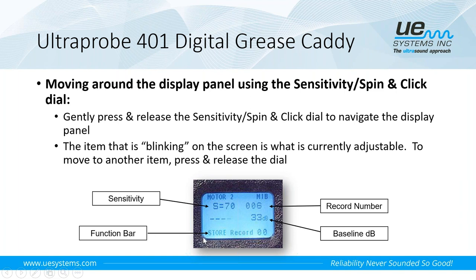And then the function bar. Whatever is down here at the bottom, in this case it says store record, is my function. If I want to store a reading for this motor 2 motor inboard bearing, I would simply press and hold the sensitivity button. Then you would see on the screen it flash up store record confirmed, and it will advance forward to the next point.